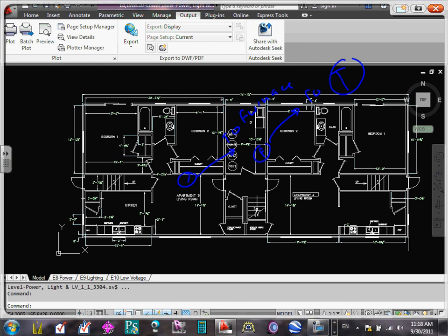The wire size that we're going to be using, guys, you're going to specify as a keynote, or you're going to put it right there. The wire they're using is 18/4. They take 18/4 wire from the furnace into the thermostat. Done. Since we don't have central air here, usually they also take 14/2 or 18/4 all the way to the furnace, to the AC. We don't have an AC; our AC is a standalone system. So 18/4 from the furnace to every thermostat in the room, done.